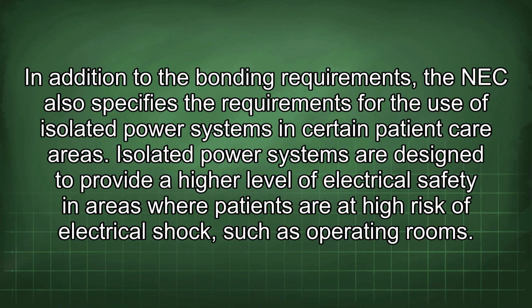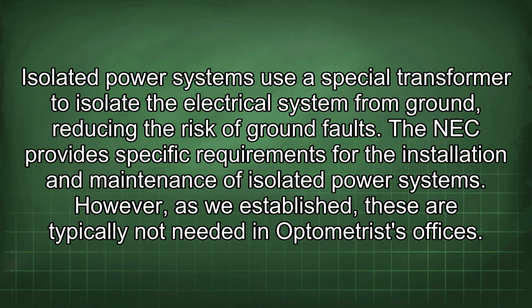In addition to the bonding requirements, the NEC also specifies the requirements for the use of isolated power systems in certain patient care areas. Isolated power systems are designed to provide a higher level of electrical safety in areas where patients are at high risk of electrical shock, such as operating rooms. Isolated power systems use a special transformer to isolate the electrical system from ground, reducing the risk of ground faults. The NEC provides specific requirements for the installation and maintenance of isolated power systems. However, as we established, these are typically not needed in optometrist offices.